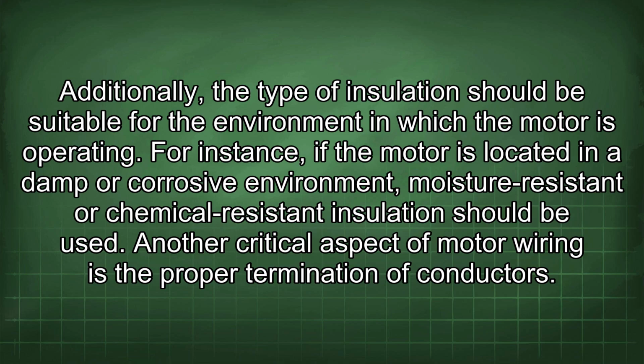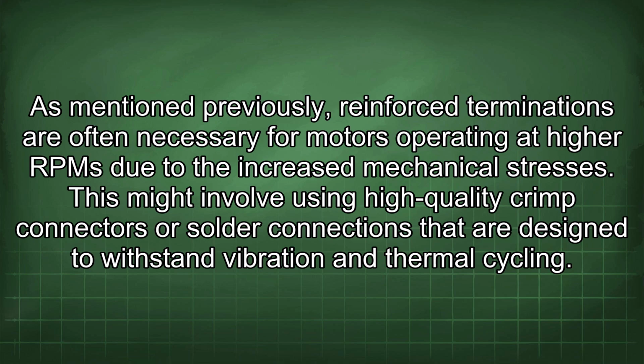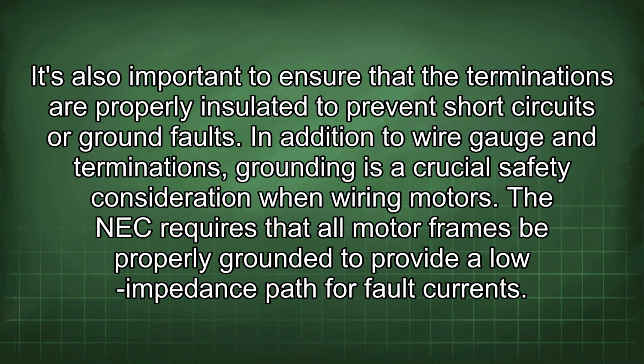Additionally, the type of insulation should be suitable for the environment in which the motor is operating. For instance, if the motor is located in a damp or corrosive environment, moisture-resistant or chemical-resistant insulation should be used. Another critical aspect of motor wiring is the proper termination of conductors. As mentioned previously, reinforced terminations are often necessary for motors operating at higher RPM due to the increased mechanical stresses. This might involve using high-quality crimp connectors or solder connections that are designed to withstand vibration and thermal cycling. It's also important to ensure that the terminations are properly insulated to prevent short circuits or ground faults.